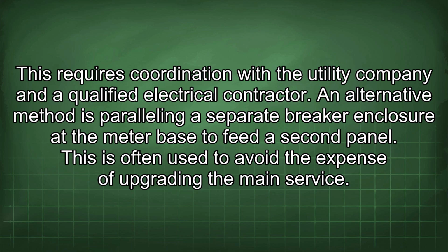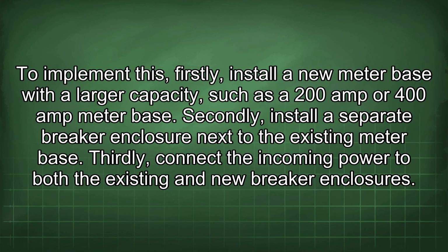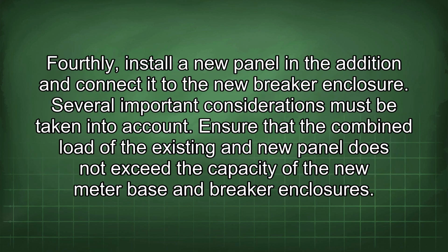An alternative method is paralleling a separate breaker enclosure at the meter base to feed a second panel. This is often used to avoid the expense of upgrading the main service. To implement this, firstly, install a new meter base with a larger capacity, such as a 200 amp or 400 amp meter base. Secondly, install a separate breaker enclosure next to the existing meter base. Thirdly, connect the incoming power to both the existing and new breaker enclosures. Fourthly, install a new panel in the addition and connect it to the new breaker enclosure.